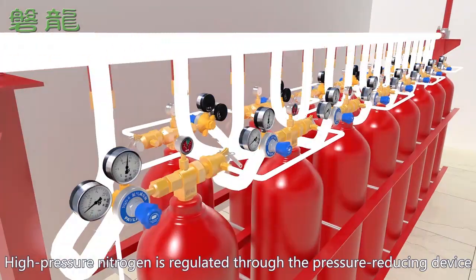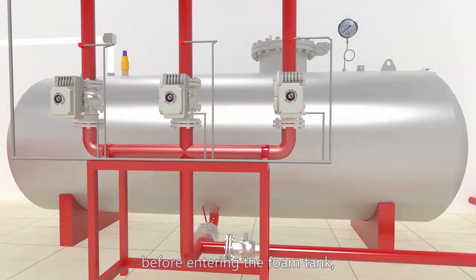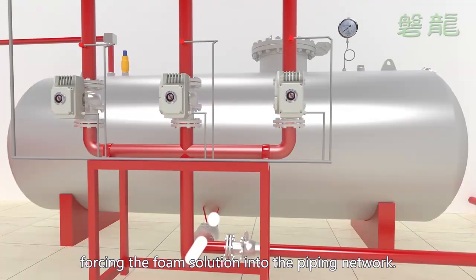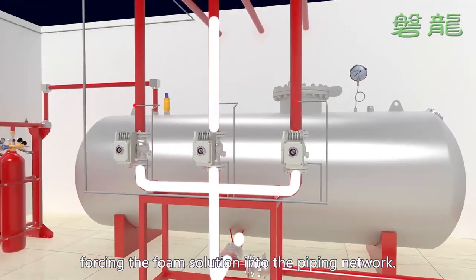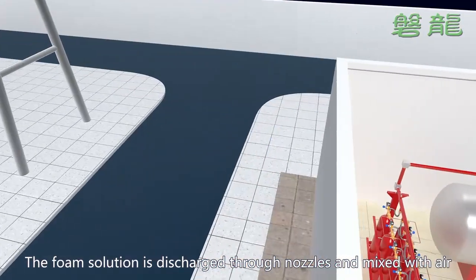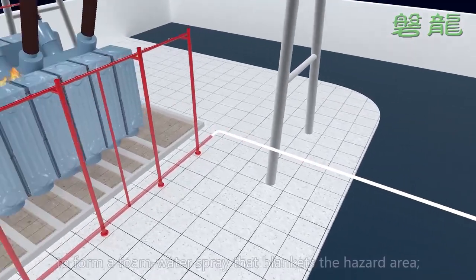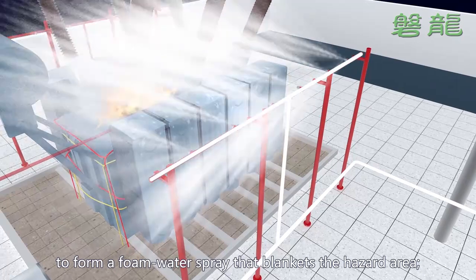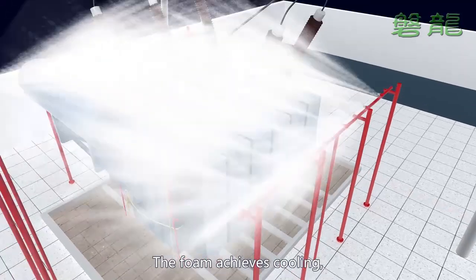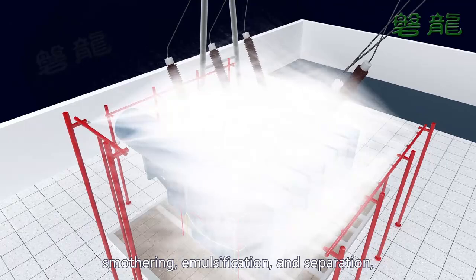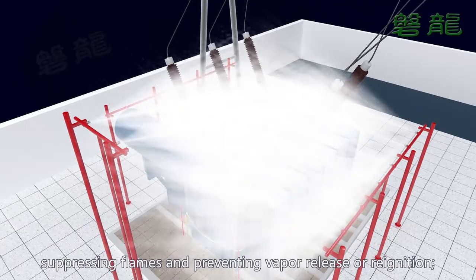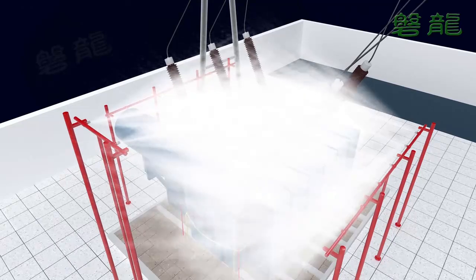High-pressure nitrogen is regulated through the pressure-reducing device before entering the foam tank, forcing the foam solution into the piping network. The foam solution is discharged through nozzles and mixed with air to form a foam water spray that blankets the hazard area. The foam achieves cooling, smothering, emulsification, and separation, suppressing flames and preventing vapor release or reignition.